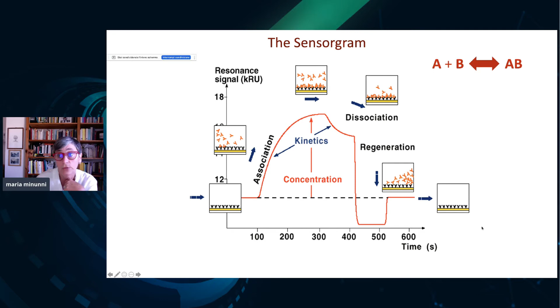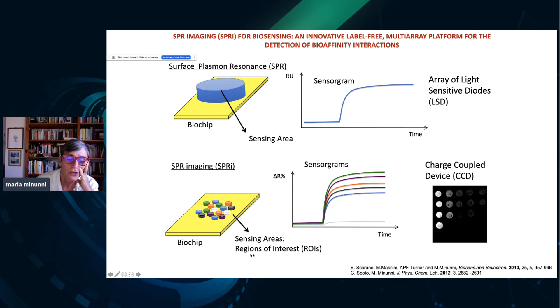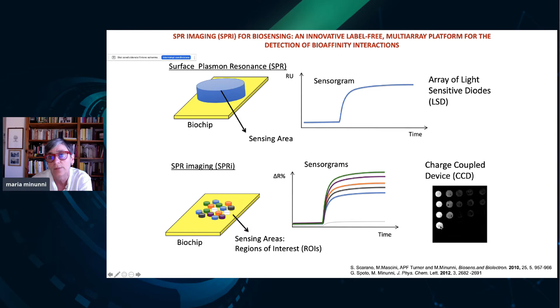So we have seen the SPR with one or a few sensing areas, which is most of the commercially available instrumentation, where the detector is an array of light-sensitive diodes. But the evolution of this instrumentation, where the principle is the same, went through SPR imaging, where you have a lot of sensing areas called regions of interest, eventually up to hundreds, and you can monitor many analytes simultaneously. Eventually, with a CCD camera, you look at the spots where you have the receptor. And this is very convenient, for example, if you have an air bubble, and to evaluate the distribution of your receptors. We'll see that in a moment on the spot.